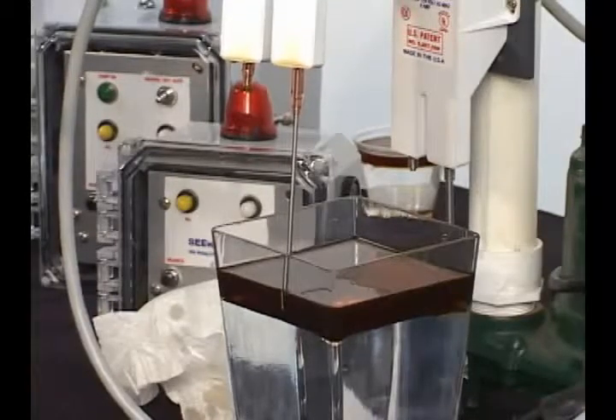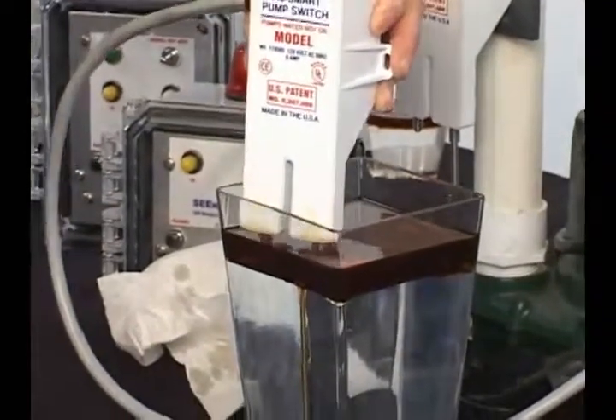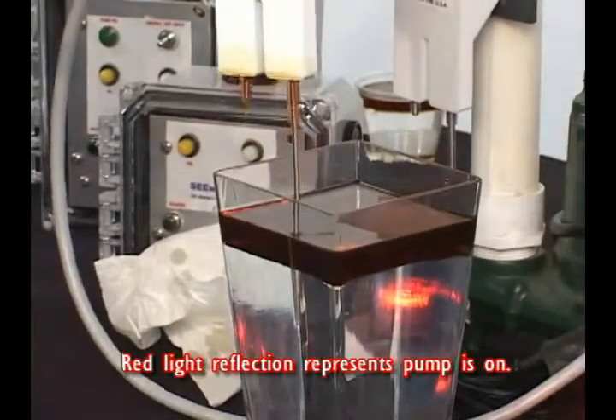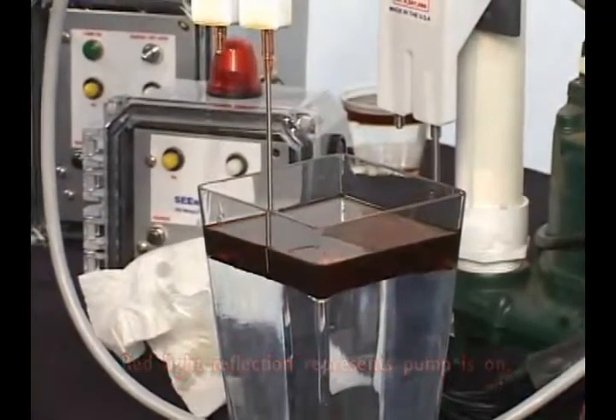I'm going to do it one more time for you. The off sensor is in oil. It goes on down through again. The on sensor goes through the oil into the water, turns on, and stays on as the water pumps down. As soon as the long sensor sees oil — or no more water — it turns off.